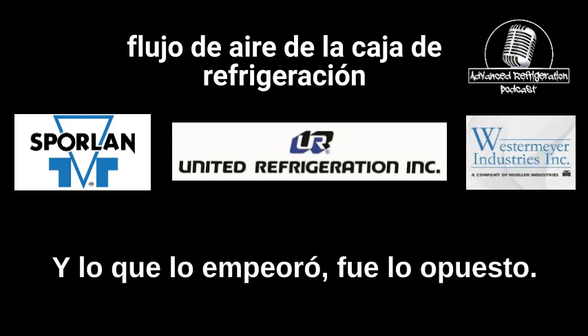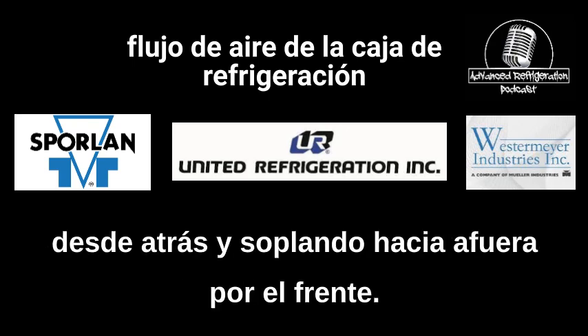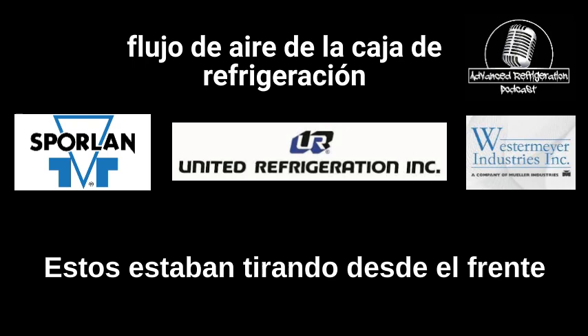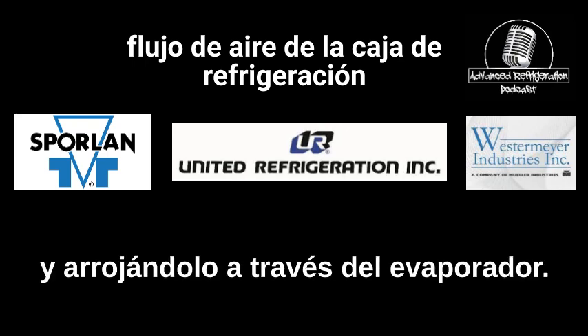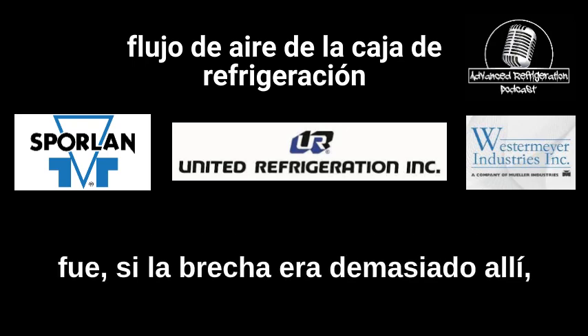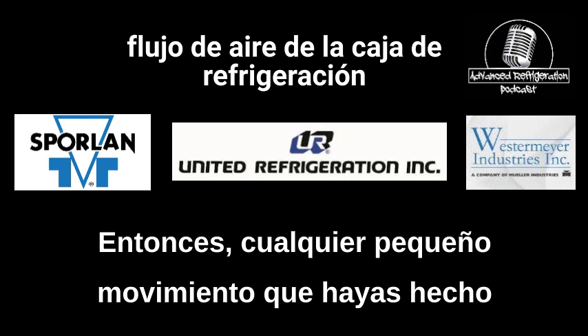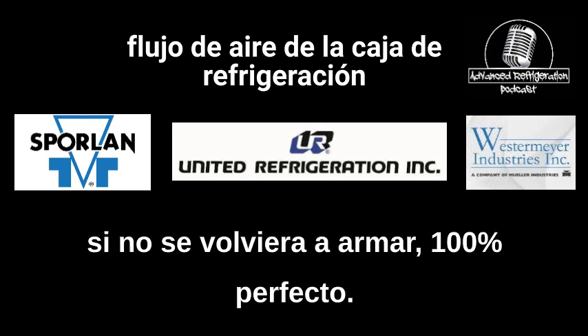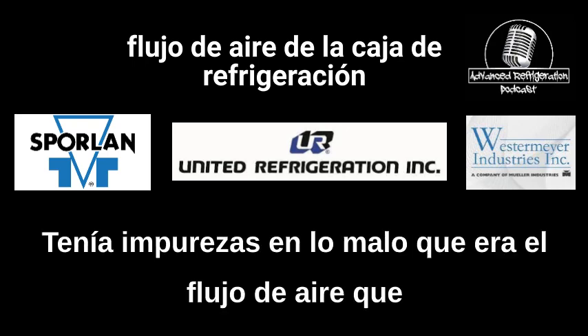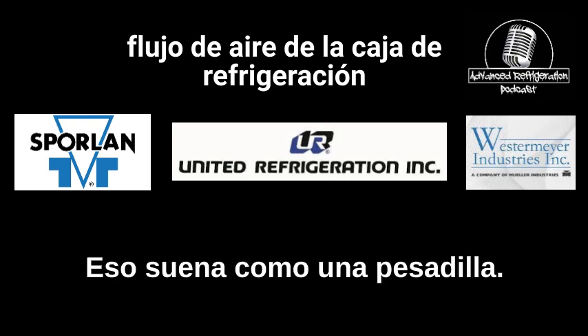And what made it worse, it was opposite. Typically on a regular evaporator, it's drawing the air from the back and blowing it out the front. These were pulling from the front and throwing it through the evaporator. And because of the way the drain pan was, if the gap was too much there, that also messed up the amount of airflow. So any small movement when putting it back together, if it wasn't put back together 100% perfect, you had impurities on how bad the airflow was, which would cause the unit to have icing issues constantly. That sounds like a nightmare.